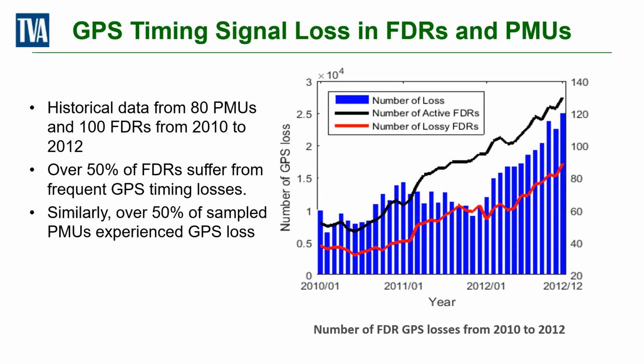One thing I want to point out: the GPS time signal is not reliable, it's weather affected, and it's subject to spoofing. Here we show that between commercial PMUs and our units, a very similar phenomenon occurred during the period we were observing, 2010 to 2012, where at least half of them had suffered GPS problems. So this is something that has to be dealt with.